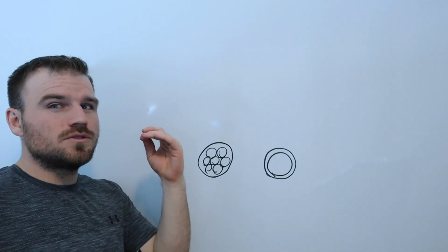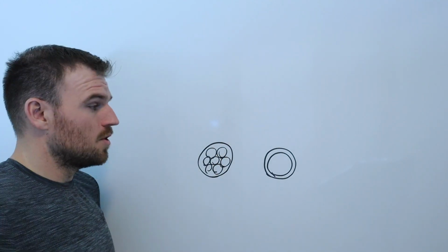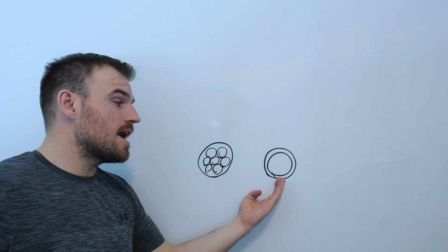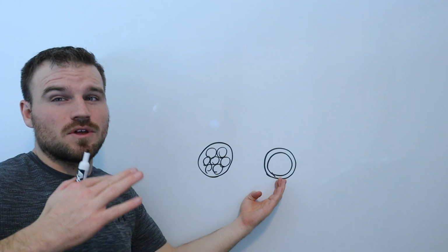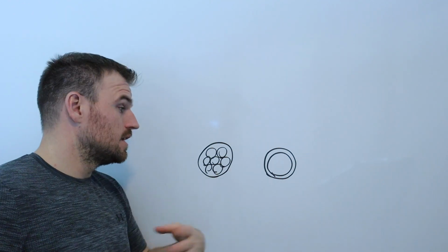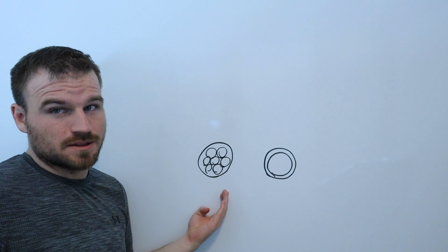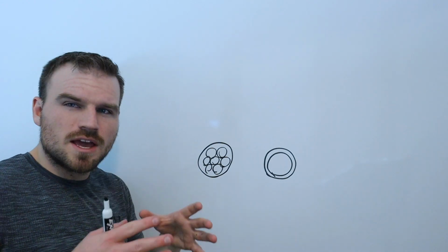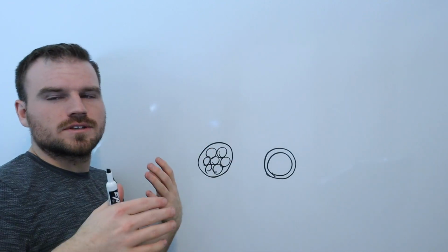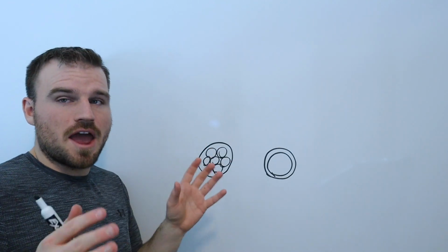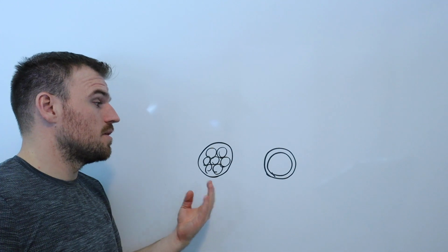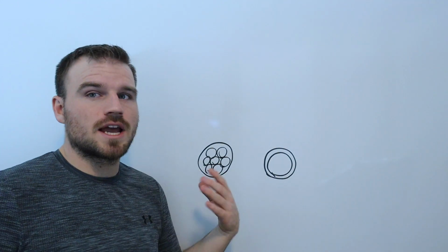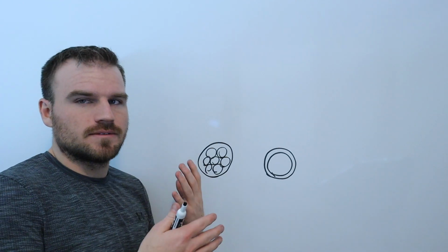The reason you might want to use one versus another one: the solid wire can handle a lot more amps. It can actually handle the flow of electricity a lot better. Now, the stranded wire, being the more popular one, is better for some rough situations. It can be flexed around. It can go around corners a lot better. It can just handle the everyday work a lot better, but it cannot handle as much electricity. So things are used kind of depending on what they need, right?